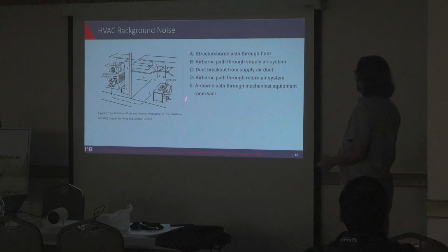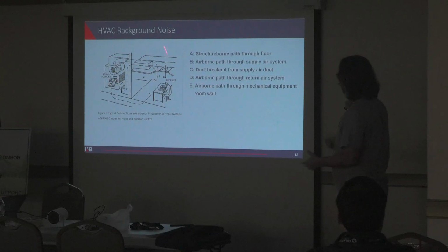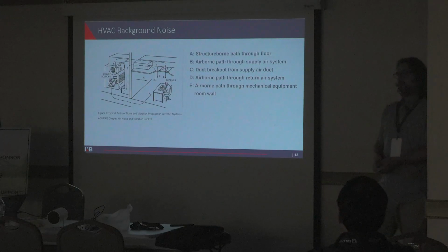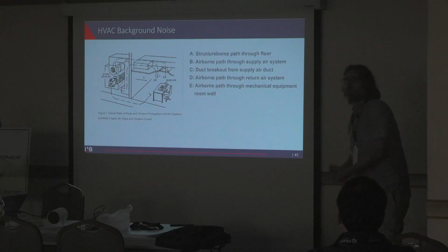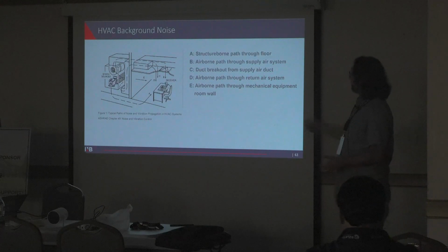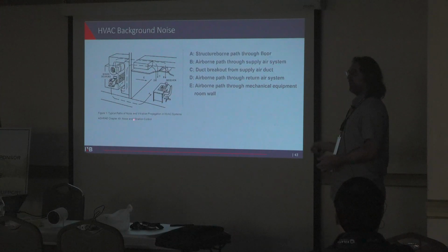So obviously, if the space doesn't have a mechanical room adjacency, we don't look at that. But for spaces that do, we look at all those considerations, and we model up each of those paths individually, and then we sum them at the end. So, for example, if this is an NC30 space, and my supply is designed to NC30, and my return is designed to NC30, and the wall is NC30, when we put them all together, we get well over NC30.